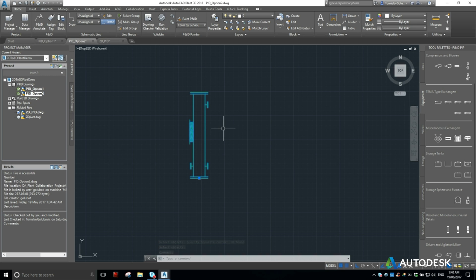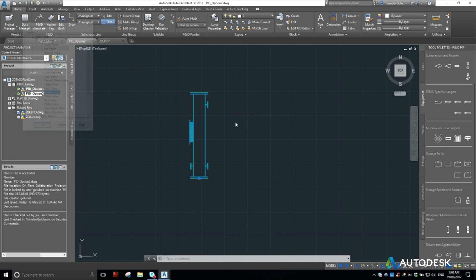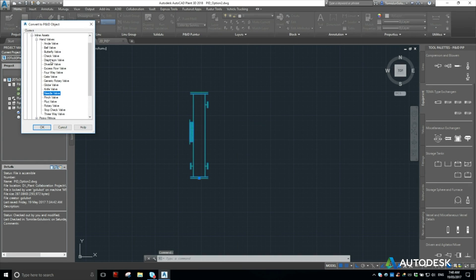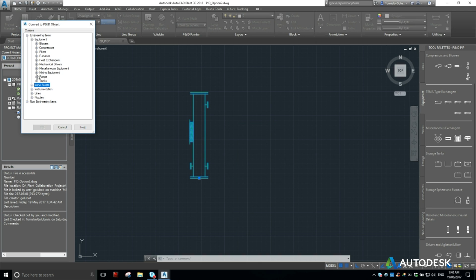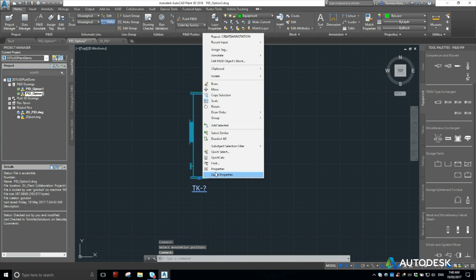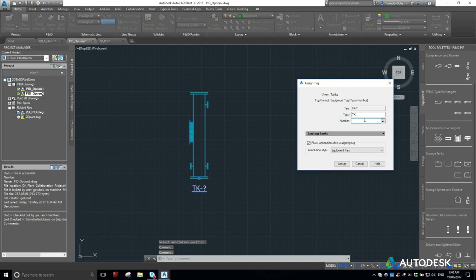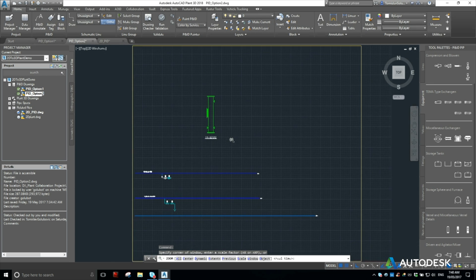To bring that as a P&ID object, we right-click on it and we say convert to P&ID object. So now it's obviously not an inline asset. We might call it pump, a tank, just a vessel. That's the class that it generates. That's going to be put into inside P&ID and then we can annotate it. And also give it a tag. So same thing, I can call this tag number TK-100. Then you can see it inherits all the properties.